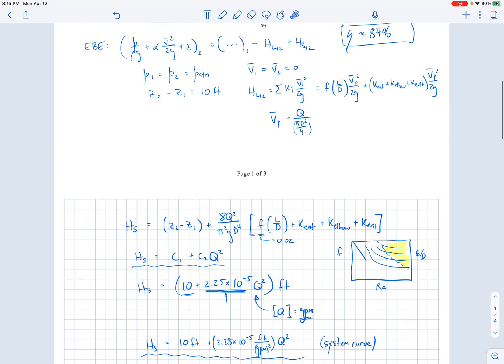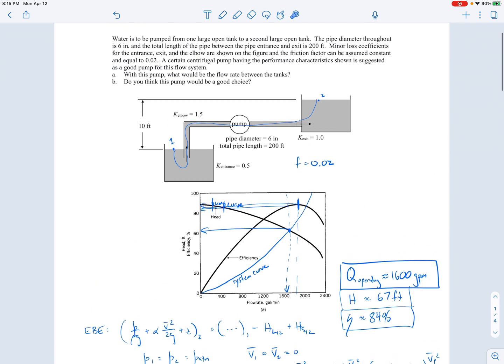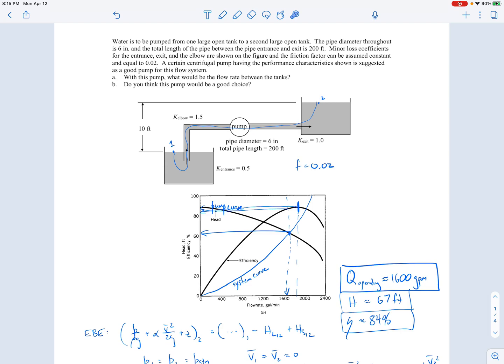That's the end of this example — a good illustration of finding the operating point for a pump in a pipe system. The key concept is that the operating point occurs at the intersection of the system curve and the pump curve, where the required head rise exactly balances the head rise provided by the pump at that flow rate. For pump selection, we check whether the operating efficiency is close to the best efficiency point; if not, a better pump choice may exist.